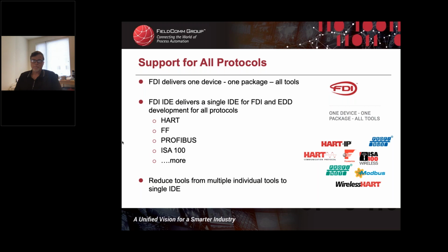Also in FDI-IDE 1.4, we have support for what we consider to be all protocols. The FDI messaging from its inception has been that it delivers one device with one package for all tools. Well, the FDI-IDE is now delivering one tool for all device developers. So you can build FDI and EDD for HART, FF, Profibus, ISA 100, Modbus, and other protocols as well. The tool can be extended for additional protocols. We have generic protocol support within the tool, so we can even add additional users of the FDI-IDE.